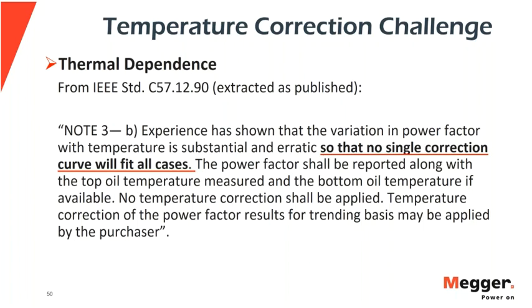I have some, but I would not raise an alarm if the slope through my line frequency power factor wasn't positive. If it was negative, I don't think I would be surprised, because the dry type transformer is prone to more conductive loss.